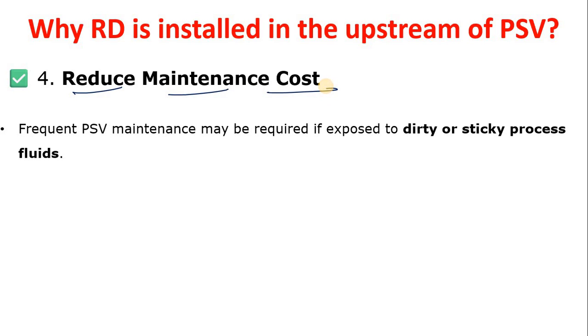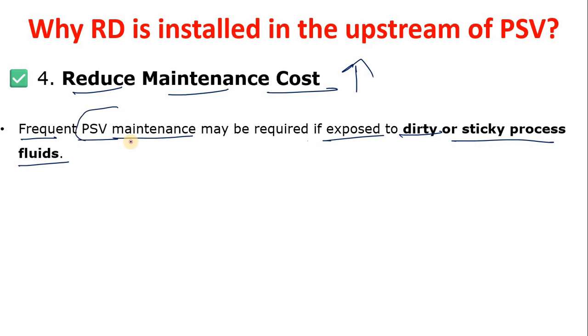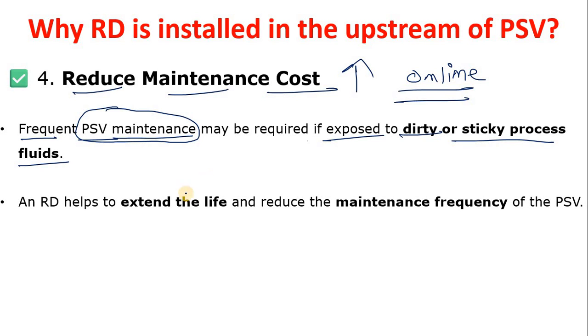The next reason is to reduce maintenance cost. If your PSV is frequently attended due to leakage or other issues, your maintenance cost increases. If the PSV internals are exposed to dirty or sticky process fluids, you may have to maintain the PSV on a very short schedule or even online. With an RD upstream, the PSV life is extended and maintenance can be deferred to a long scheduled shutdown or annual turnaround.